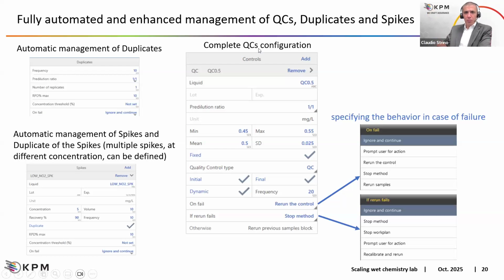Concerning QCs, we can define all the main info: the target value and standard deviation, and the software will automatically calculate the minimum and maximum value, the acceptance range. Or we can define the acceptance range and the software will automatically calculate the target value and the standard deviation. A QC can also be scheduled as per our need: initial means before running samples, final at the end of the analytical routine, and dynamic with frequency means after how many samples we want the automatic scheduling of the QC.